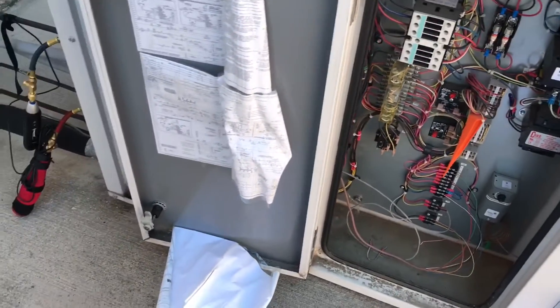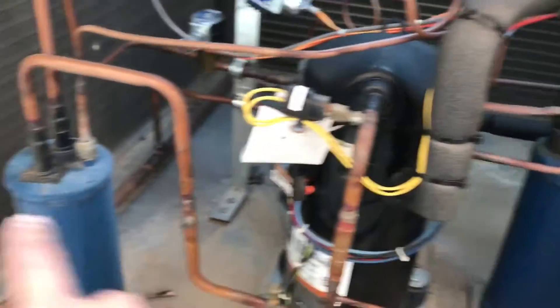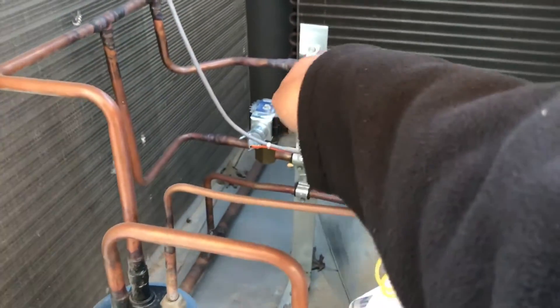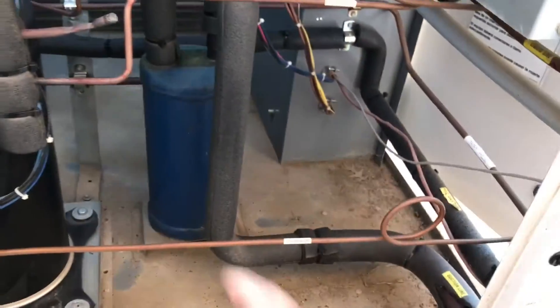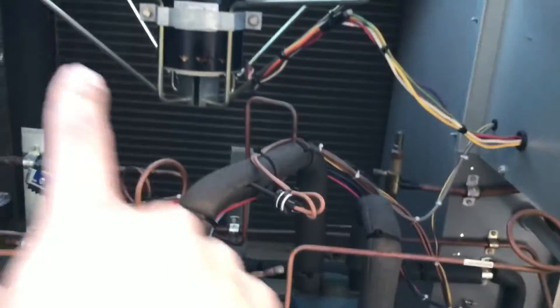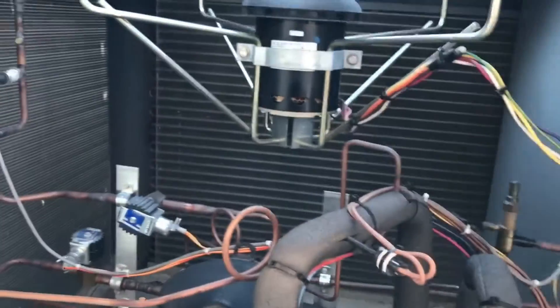I've disconnected the reheat coil. So we have your compressor, your oil separator. I believe that's your reheat and hot gas bypass. Accumulator. It's got a speed controller for the fan.